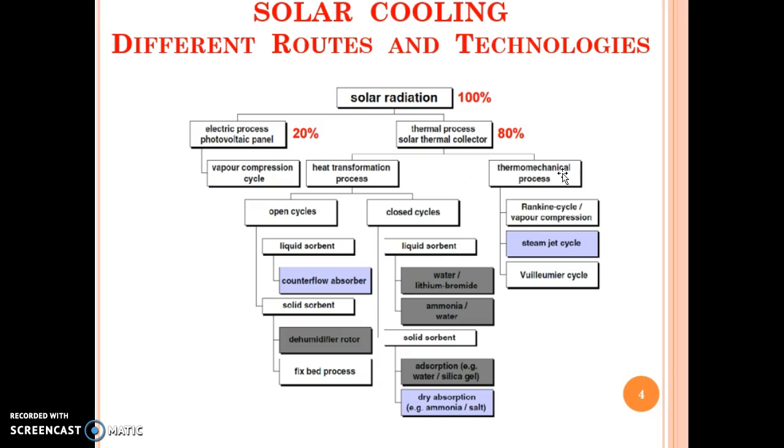One of the categories is heat transformation process, another is thermo-mechanical process. We are going to focus on heat transformation processes where it can be done in an open cycle or in a closed cycle. In open cycle you have options like liquid desiccant and solid desiccants. In closed cycle you have options like liquid sorbent and solid sorbent, which are nothing but vapor absorption and vapor adsorption technologies.